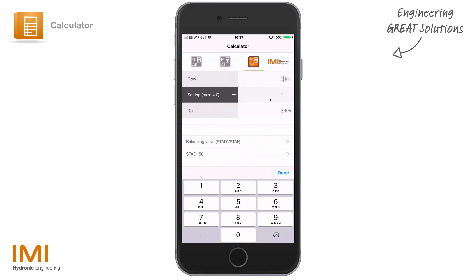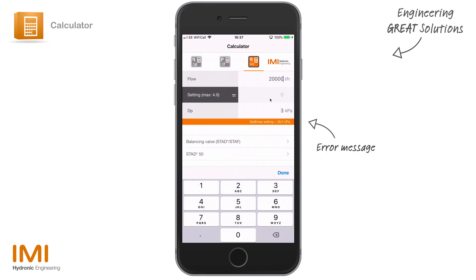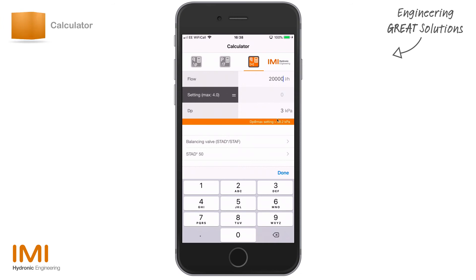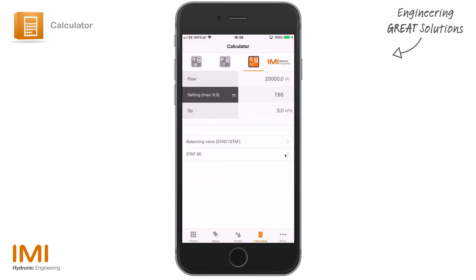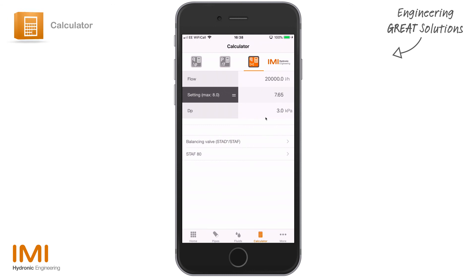If you put in something that's too much, you might see a warning flash up. It's not really an error — the delta P at the maximum setting of the valve, which happens to be four turns in this instance, would be 38 kPa. So what we're seeing here is our valve is massively undersized. If we then select a valve of a bigger size, we can see the valve is now selected for 3 kPa, with the setting almost fully open at 7.65 turns of eight — much more appropriately sized — and the warning has now disappeared.